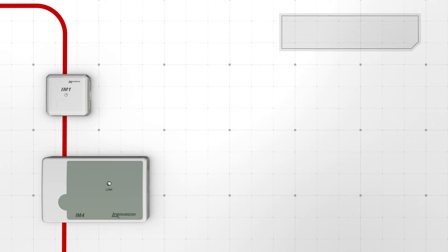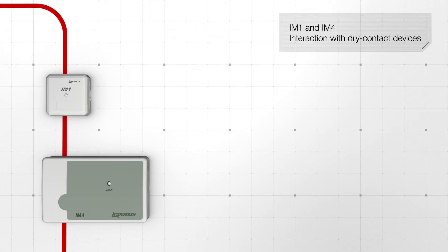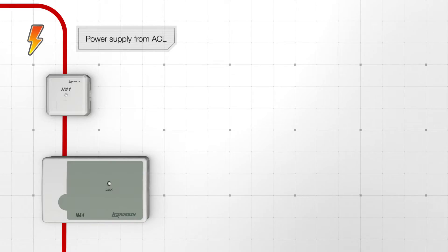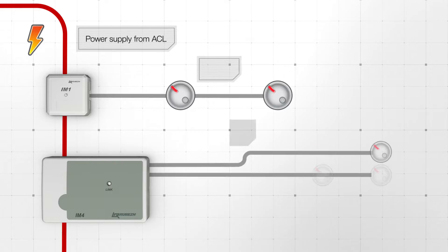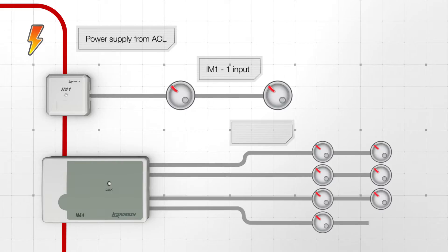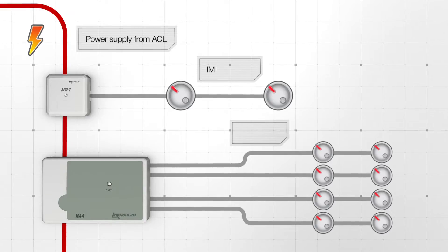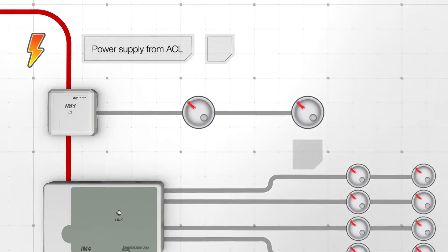IM1 and IM4 are used for interaction with dry contact devices. IM1 and IM4 input modules are powered by the addressable communication line. IM1 has one input and IM4 has four inputs. The input can be configured both as a fire alarm input or as a process input.